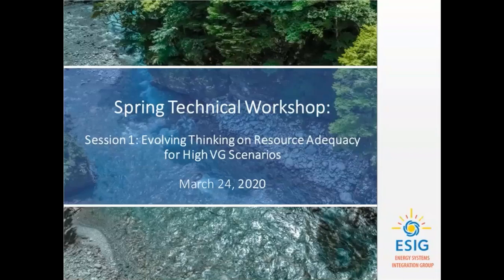Some of the other key trends that have been popping up with resource adequacy, and really the motivation behind this panel, are these. With more renewables in the system, we need to start thinking about not just peak load, but net peak load, so looking at load minus the contribution from wind and solar resources. We need to look at more hours of the year, what's been touted by some entities as all hours matter. So not just looking at summer afternoons, but considering hours throughout the full year.